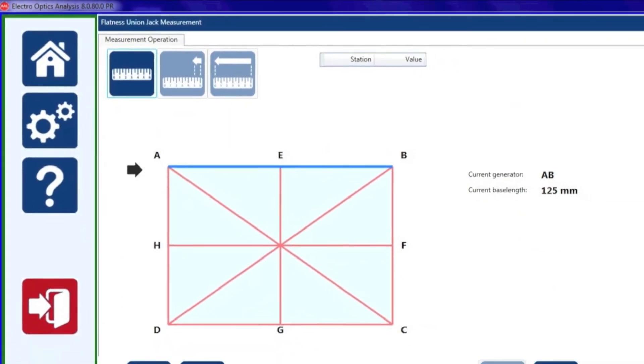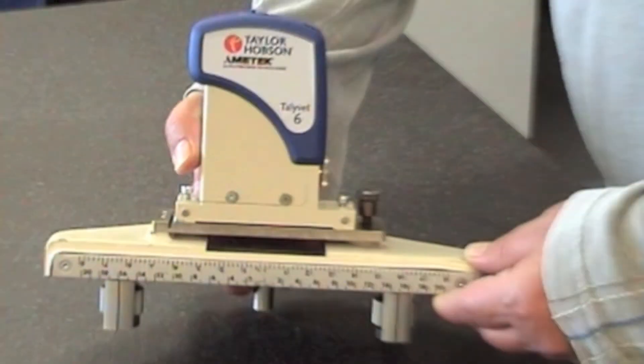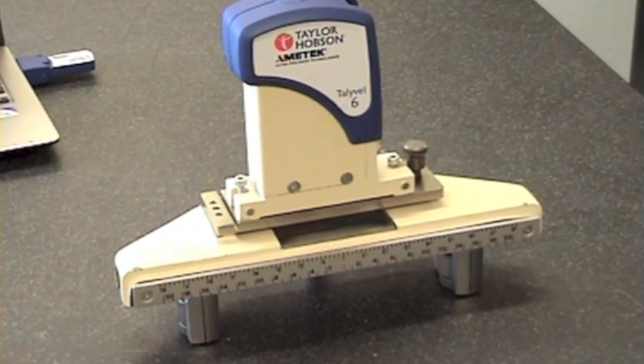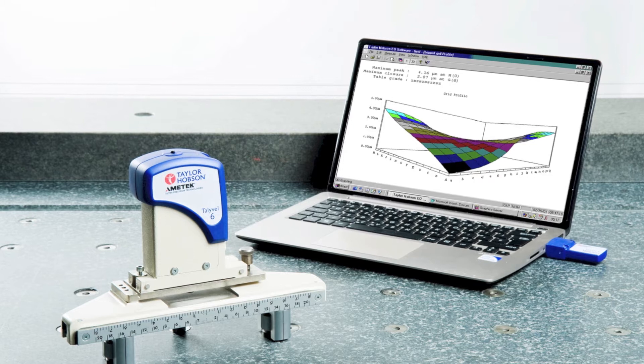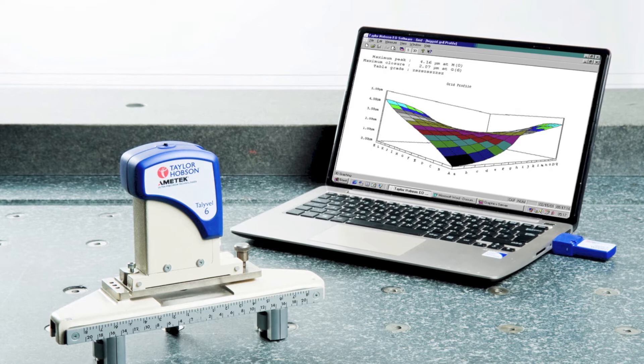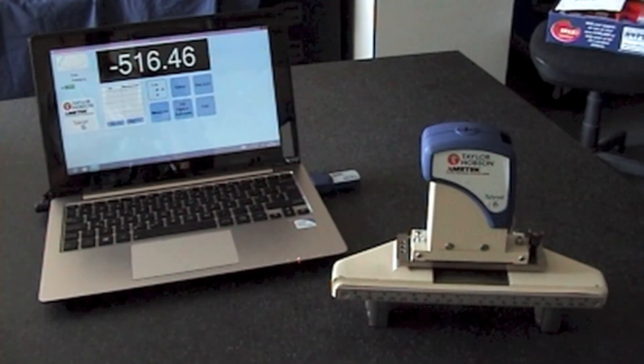The first thing we have to do is determine the size of the table and then how many points per line we're going to need. When measuring the table size we have to take about an inch off the edge because of the feet on the adjustable base. The software now knows the size of the table and how many points per line you need, so it will tell you what to set your adjustable base to. There is some adjustment for tilt on the adjustable base so you can actually zero the Talyvel before you start your measurements.